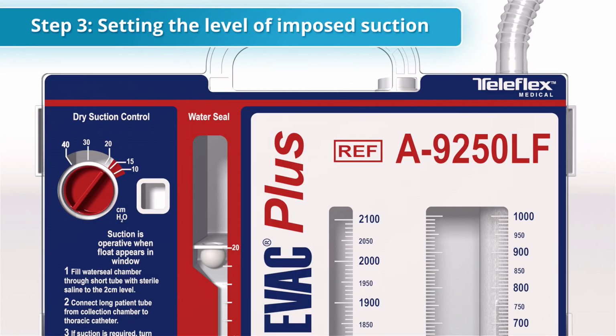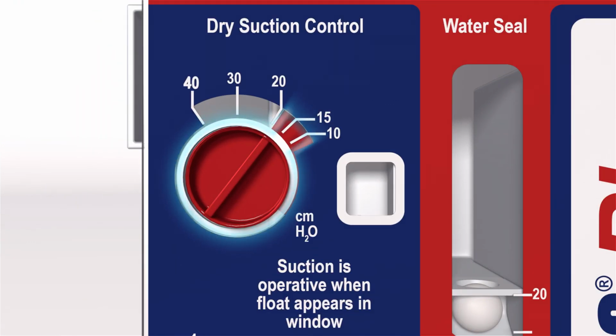The third step in setup, if suction is prescribed, is selecting the level of imposed suction. Both the A9250LF and the S1150-08LF utilize dry suction technology, which means no water is required to operate suction control. A dial is used to set the desired suction level. This is conveniently preset at the -20 centimeters of water setting. If a different level of imposed suction is prescribed, rotate the dial until it clicks into place at the desired level. 5 settings are possible: -10, -15, -20, -30, and -40 centimeters.